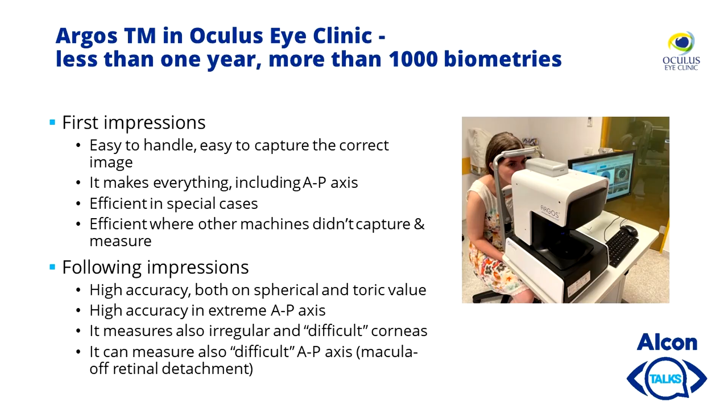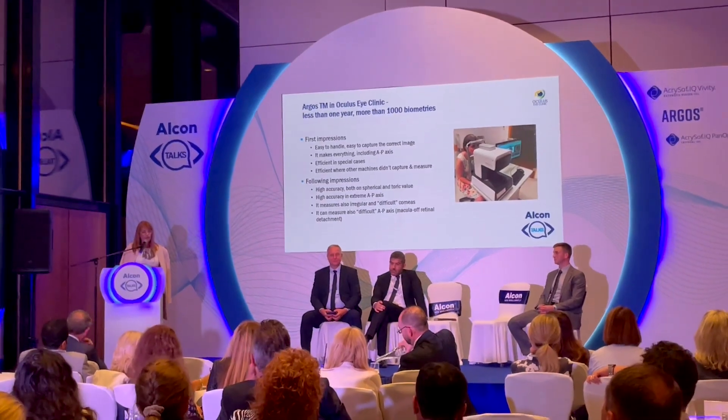Our first impressions were that it is very easy to handle, easy to capture the correct image, and it measures everything including the anterior-posterior axis, which Verion for example didn't do. It was efficient in special cases where other machines failed to capture and measure. Subsequent months showed us high accuracy for both spherical and toric values, high accuracy in extreme axes — longer or shorter eyes — and it can also measure irregular and difficult corneas, including difficult anterior-posterior axis cases like macula-off retinal detachment.